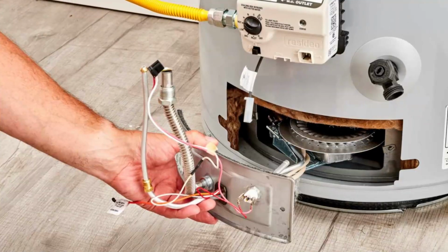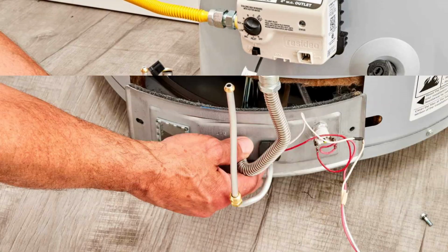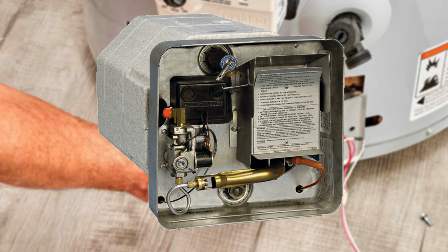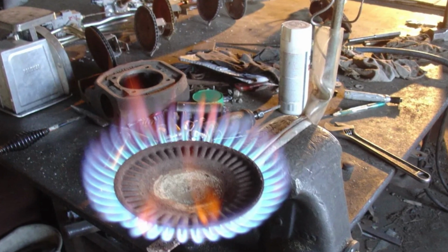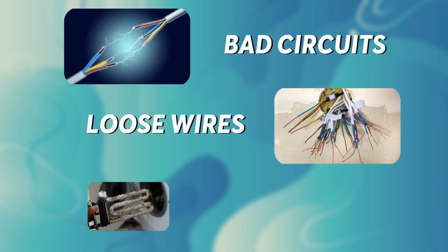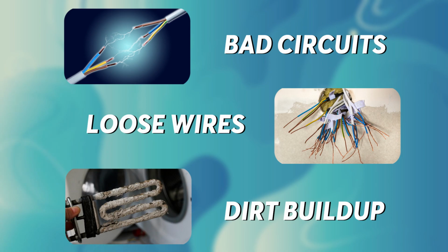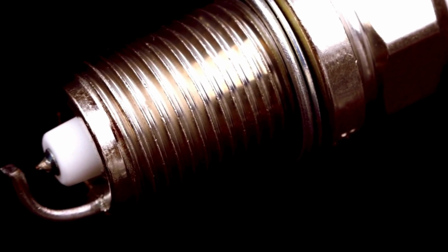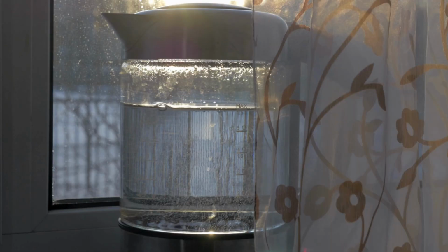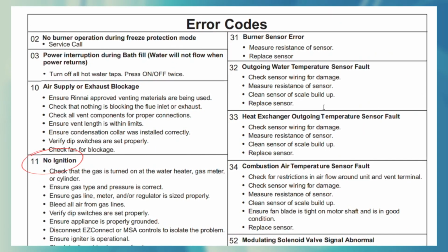The following are some of the common causes for this error code. Faulty igniter. The Rinnai water heater's igniter is usually located at the bottom of the water tank and is crucial since it ignites the gas burner. If it's faulty from bad circuits, loose wires, dirt buildup, or insufficient voltage, the system will have no ignition, and water will not be heated, leading to an error code 11.